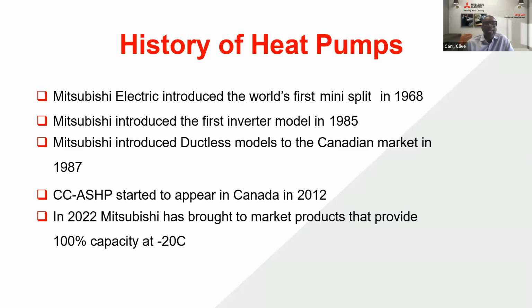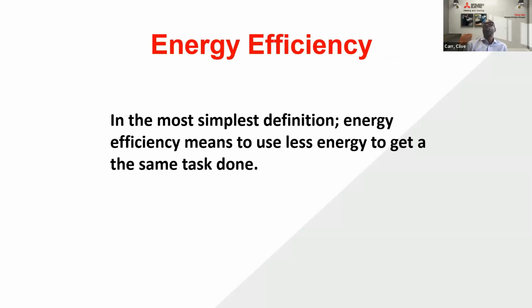It operates to an extended range of minus 30, where at minus 30, you're pretty much getting approximately 70-85% of your rated capacity. So it's able to maintain the heating capacity. What does this mean? This means that you can now use the heat pump system as the primary and only heating system, because you'll be able to maintain all of the heating capacity down to your winter design temperature. So you're able to now size heat pumps as the primary and only heating system within the space.